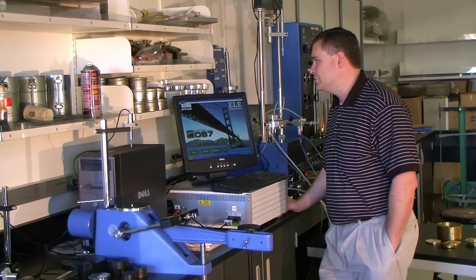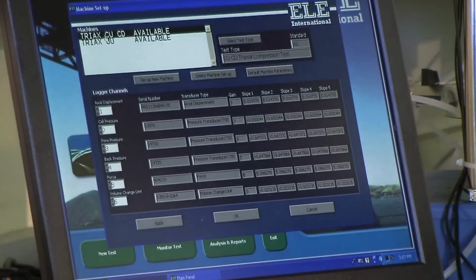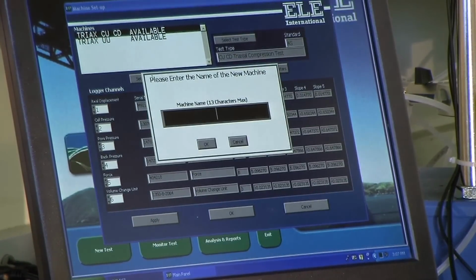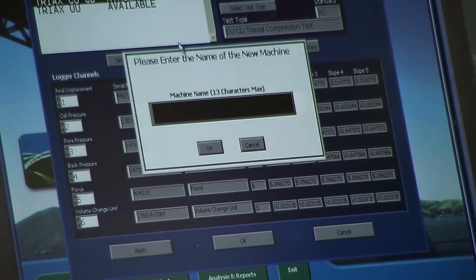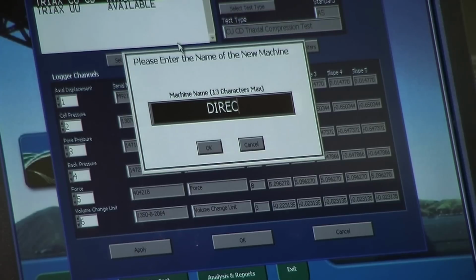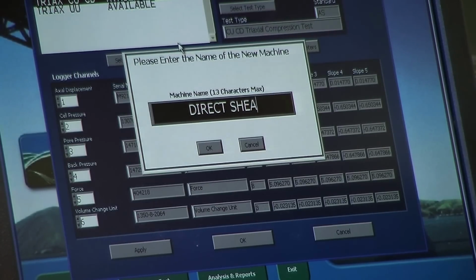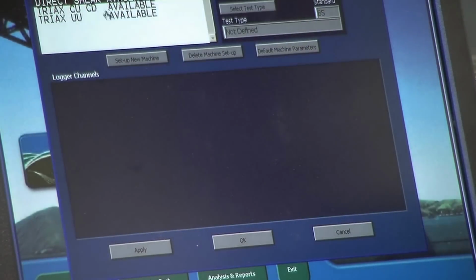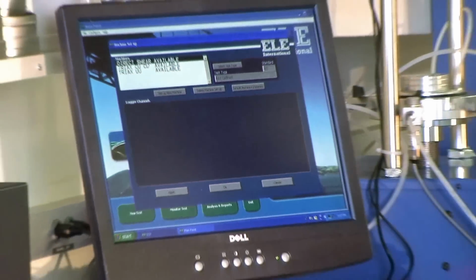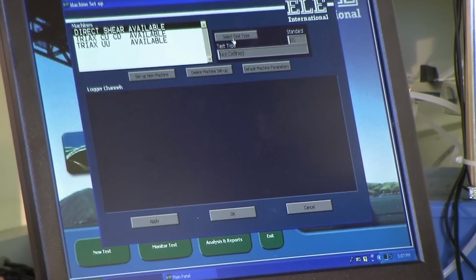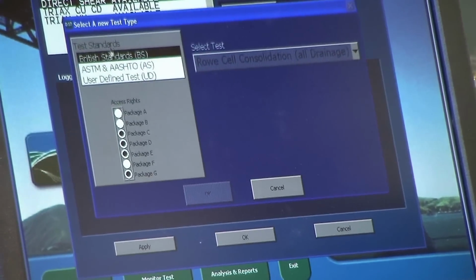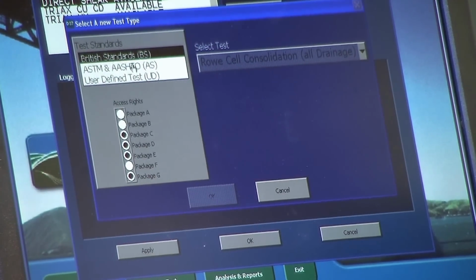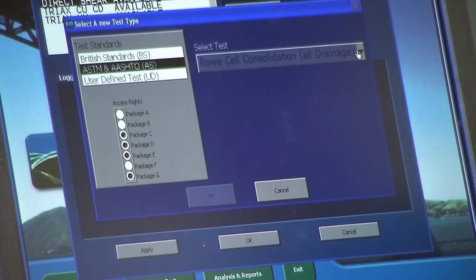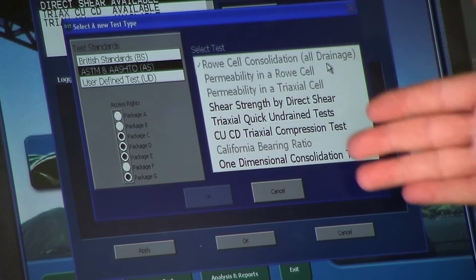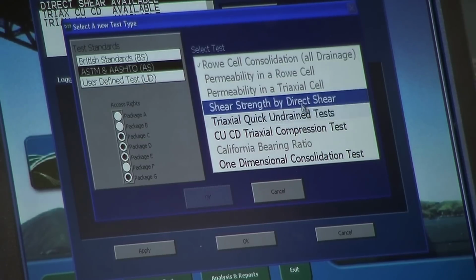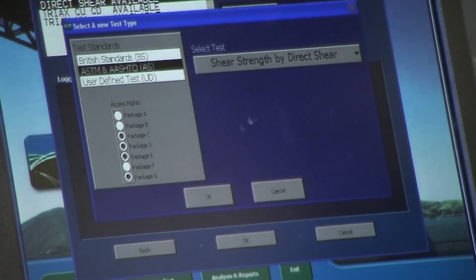Now the next step is to generate a machine. We already have the triaxial machines generated, but let's go ahead and set up a new machine. Click the new Set Up New Machine button. Enter in the name for the new machine. We'll call this Direct Shear. Click OK. And then click on the Direct Shear here on the left side. And then you want to go over just to the right of it, select Test Type. Click that button. We're not using British Standard, we're using the ASTM standard. Then click the drop menu, and this shows you which tests the customer has purchased, the modules that they've purchased. We're going to do shear strength by direct shear for this one.